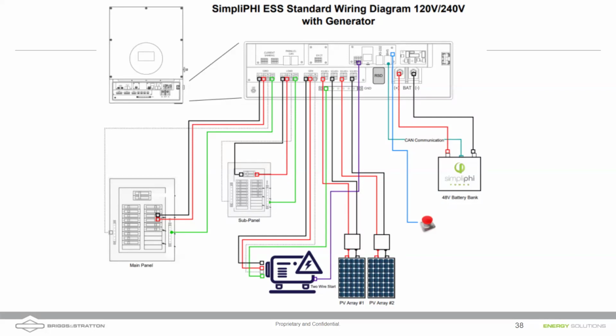But we have had instances where lower quality signals get rejected by the inverter. Those inverters do expect a good quality signal to be coming in. That means that frequency has to be in the right range. And as you load your generators heavily, that frequency drops, as you know. So you have to make sure that it stays within the acceptable range for an inverter. Most inverters do have a wide tolerance setting. The SolArk and the Briggs & Stratton inverters have this wide tolerance setting, but you still want to be within a few hertz of 60 hertz with a loaded generator.